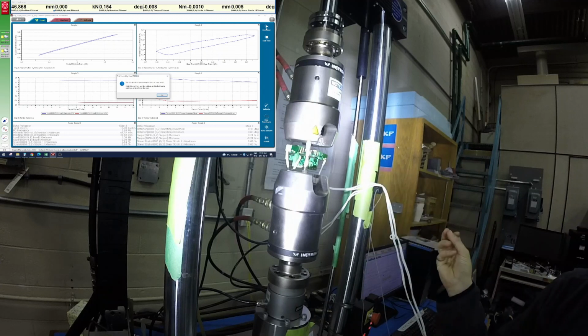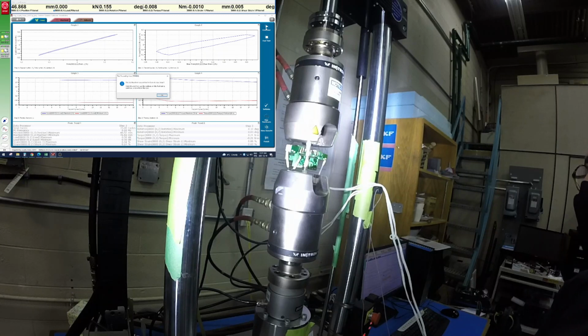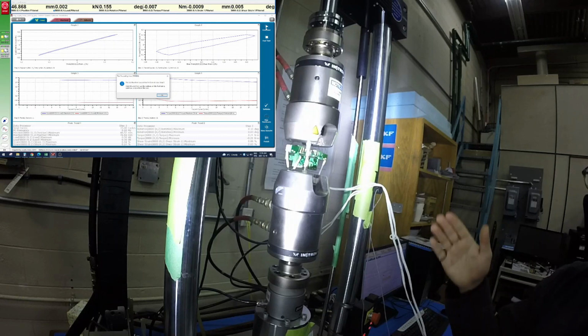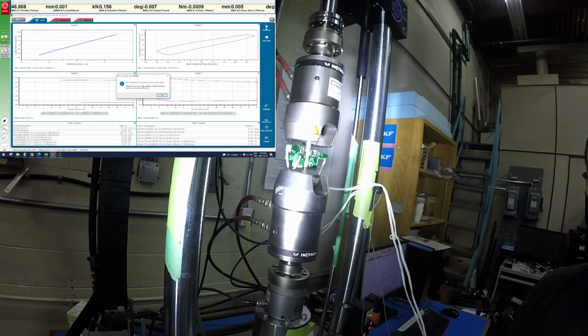If you want to remove the sample and say you have to give the machine to somebody else, or you have to shut down the machine due to a power outage or a vacation break or something like that, you want to make sure that you're not leaving the test unattended, where it can potentially go unstable if there's a hydraulic system update or a power outage or something like that. So that is something you want to make sure that you're diligent of. But other than that, this is a complete summary of how to run a biaxial test in force control mode and torque control mode, but monitoring the strain using the biaxial extensometer.